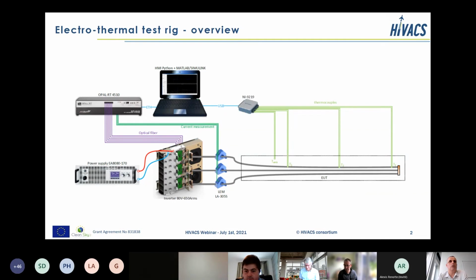So you see the electrical architecture in this slide. At the bottom right, you see the cables that we will test. So the three-phase cable: on one side, we connect the three phases to a voltage inverter, and on the other side, we connect together the three conductors. We short-circuit them with a bus bar. The inverter is driven by our own control laws. We developed our control laws, our regulation and our PWM strategy, in an Opal-RT platform that can drive the inverter and impose the current we want in the conductor. We then use a classical acquisition system to get all the sensors, and we drive all of this with a computer.